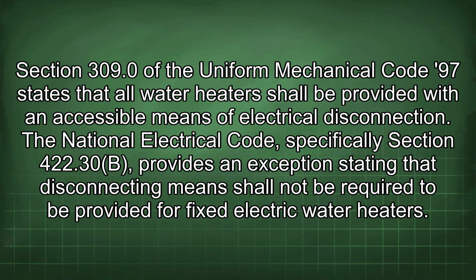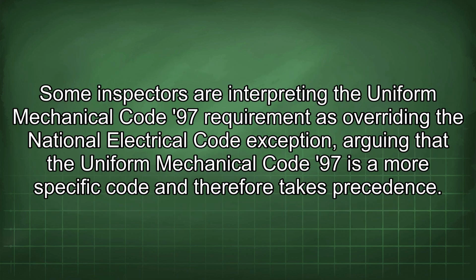Section 309.0 of the Uniform Mechanical Code 97 states that all water heaters shall be provided with an accessible means of electrical disconnection. The National Electrical Code, specifically Section 422.30b, provides an exception stating that disconnecting means shall not be required to be provided for fixed electric water heaters. Some inspectors are interpreting the Uniform Mechanical Code 97 requirement as overriding the National Electrical Code exception, arguing that the Uniform Mechanical Code 97 is a more specific code and therefore takes precedence.